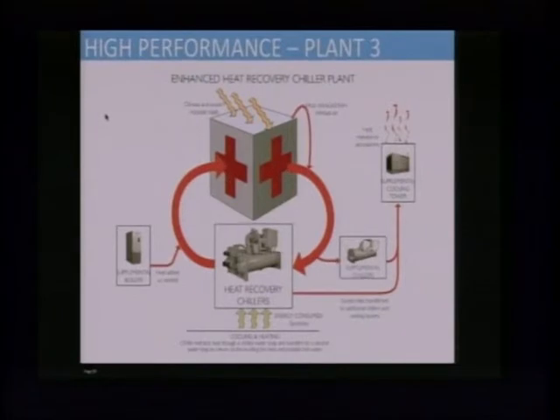So here the chiller and the boiler are working together to be a more efficient system. We've added a supplemental boiler and a supplemental chiller here. I mention that because probably most of the time the heat recovery chiller would be enough, but there are some peak moments during the year where more chiller or more boiler is needed. As a team, when we were making decisions like this, we always took the more conservative road because we didn't want to artificially deflate the cost model. We wanted to include elements like this that may increase the cost a little, but make it a more robust system.